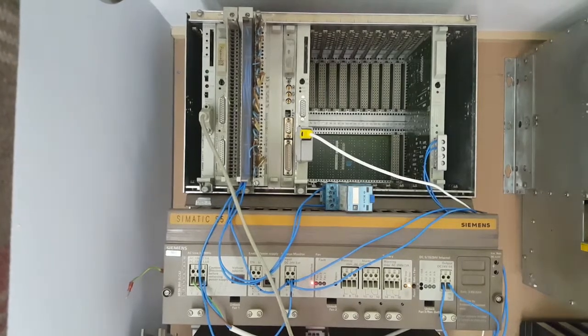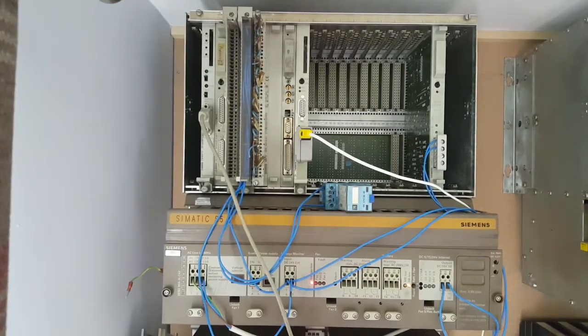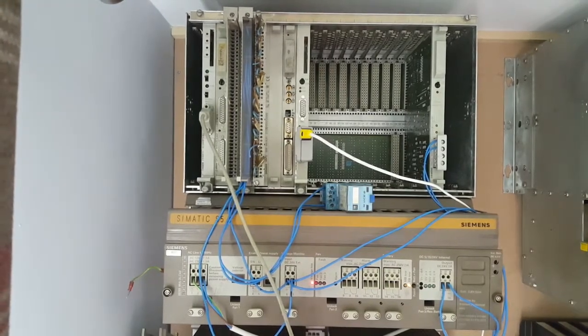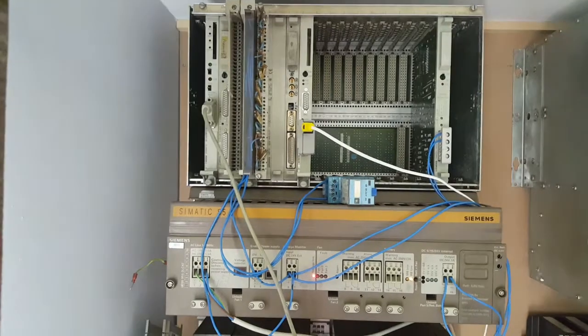The CP1430 card is of compact design, so it can be fitted into a Siemens S5 115U using an adapter case, a 135U or a 155U PLC. As can be seen here, it is installed in a Siemens S5 135U PLC in slot 9. In this particular rack, the card can be seated in any of the first 9 slots only.